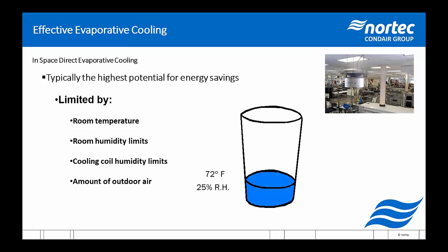We have to watch cooling coil humidity limits, which I will touch on in a minute. And we also have to watch the amount of outdoor air. And that's because if we don't have enough outdoor air, we can't humidify. We end up over-humidifying the space. So we can only humidify the amount of outdoor air coming in. Now I've got this little cup here at 25% RH at 72 degrees Fahrenheit. The reason the room temperature and room humidity limits are better for in-space direct evaporative cooling as opposed to in-duct evaporative cooling is because we have a lot more space to fill this cup, per se.